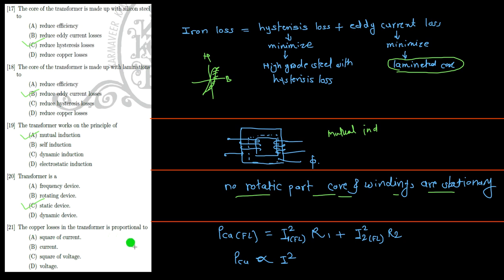The copper losses in the transformer are proportional to, so copper loss is always I square R. So keep in mind the loss is always proportional to the current square. So square of the current, don't give the answer current, because it is not directly proportional to current, it is proportional to the square of current. It is not proportional to the voltage, or to the square of the voltage. So the correct answer is what? Square of current. Hope you get all these answers.